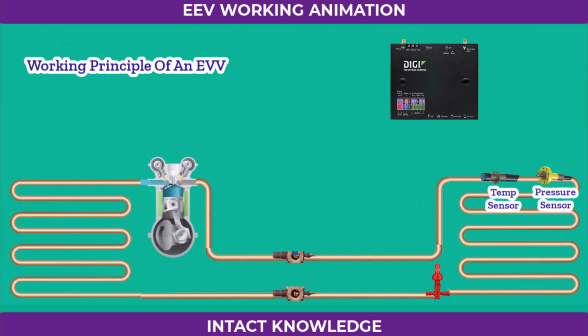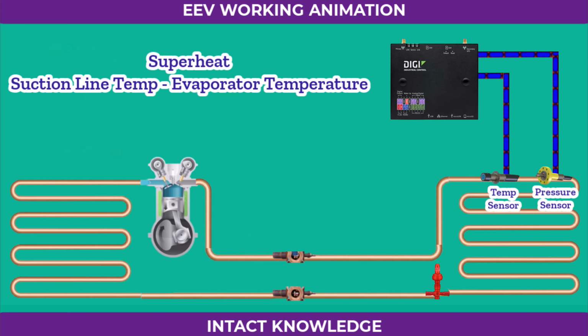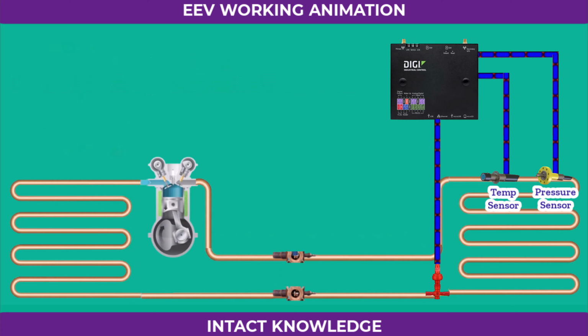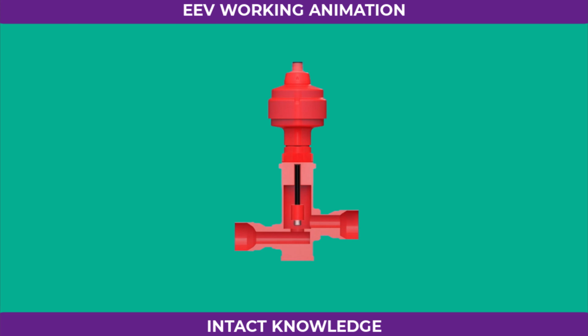Now let's see how an electronic expansion valve works. The controller collects pressure and temperature readings from the sensors. It then calculates the superheat, which is the difference between the suction line temperature and the evaporating temperature. Based on this value, the controller sends an electrical command to the stepper motor. The motor turns a specific number of steps, moving the needle in or out, which adjusts the valve's opening and controls how much refrigerant enters the evaporator.